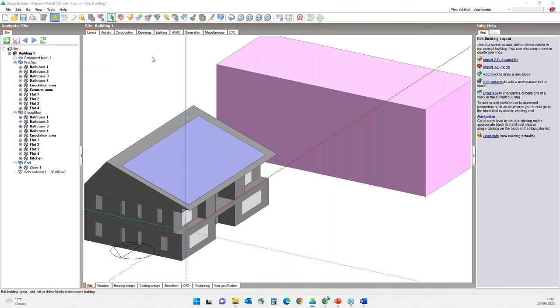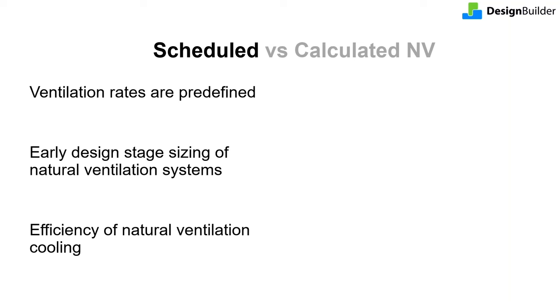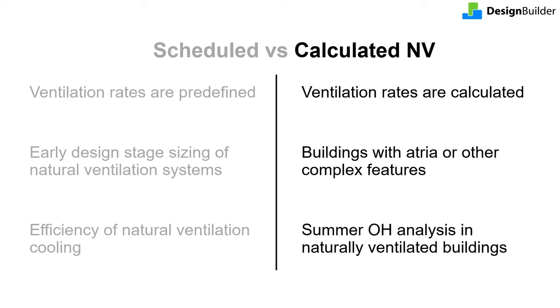There are two general approaches to natural ventilation and infiltration modelling in DesignBuilder, depending on the option selected under the natural ventilation and infiltration header in model options. Schedule is the default option — here we set the airflow in air changes per hour and set a schedule to adjust it. It is useful for early stage sizing and assessing natural pre-cooling efficiency. When the calculated option is selected, you define the openings, controls and weather details, and EnergyPlus calculates the airflow using wind and buoyancy driven pressures, opening sizes, operation, and fabric infiltration details.